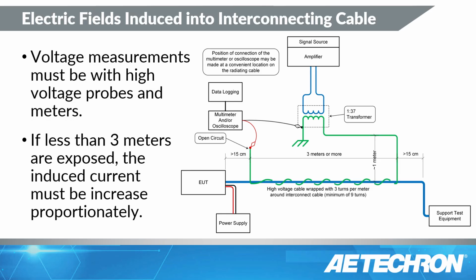Now, for this test, the wire is wrapped around the equipment, and the requirement is to have 3 turns per meter. Keep it about that. Don't wrap it real tight, 20 turns around there. There's no need to do that. Just three turns per meter. It's going to be 9 turns across 3 meters. That's entirely adequate. Just make sure that you do wrap it and keep the wire as close as possible to the cable under test. Again, 15 centimeters from the unit.